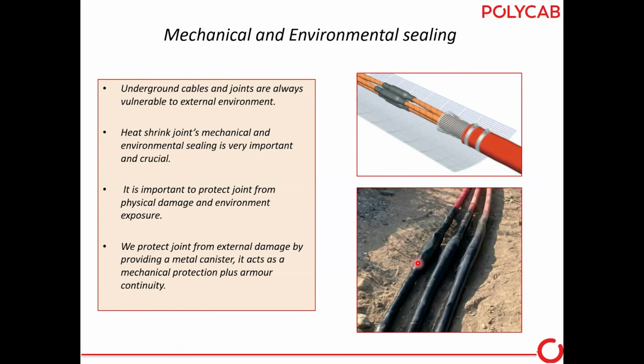It should not be allowed. Like in Mumbai or coastal areas, the water table is very high, and these joints are always vulnerable to water going inside the joints and terminations. So the outer sleeves must always shrink onto the cable in such a way that water should not go in from that point.